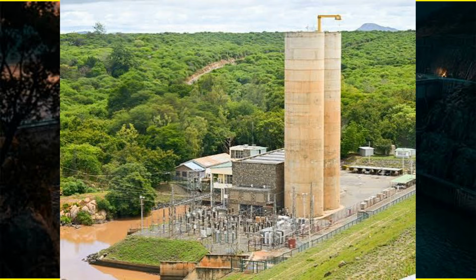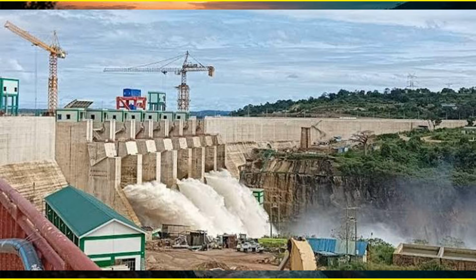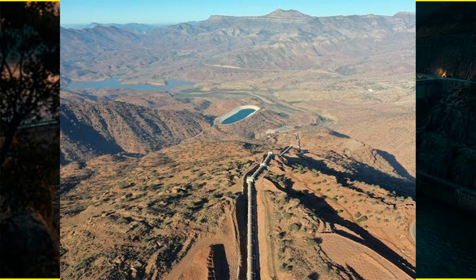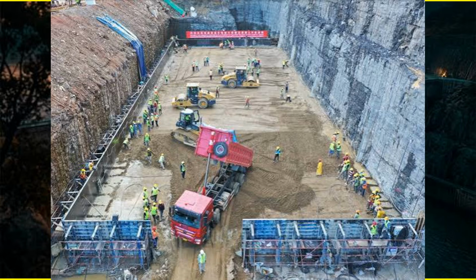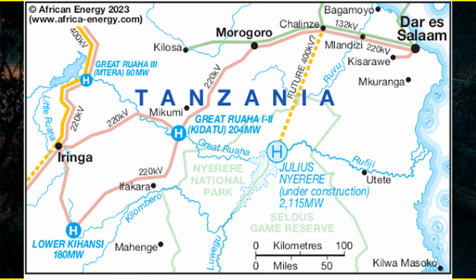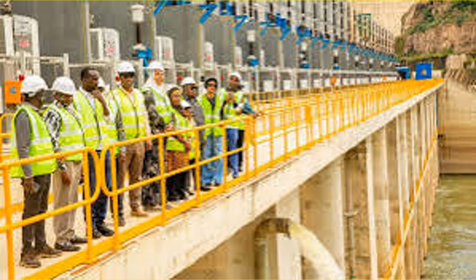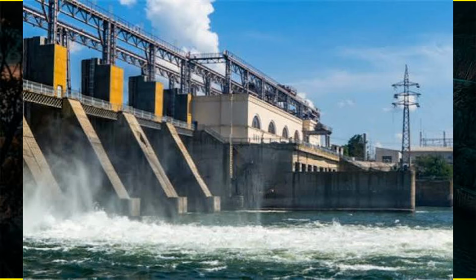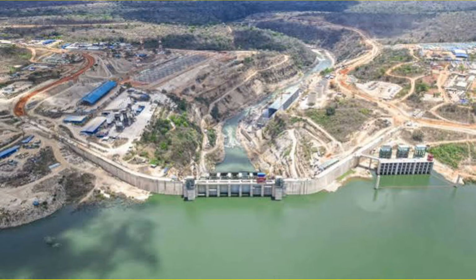There is also the less glamorous operational issue of maintaining a plant of this scale. Nine large turbine generator sets, high voltage switchgear, spillways, gates, transformers, and kilometers of associated infrastructure require a permanent program of preventive maintenance. The real test of the Julius Nyerere Hydropower Project will therefore not be whether all 9 turbines can run simultaneously during an inaugural demonstration. It will be whether they remain available, safe, and economically productive 10, 20, or even 40 years from now.